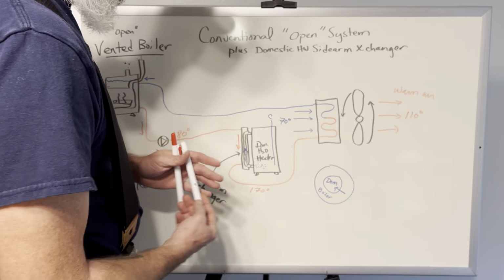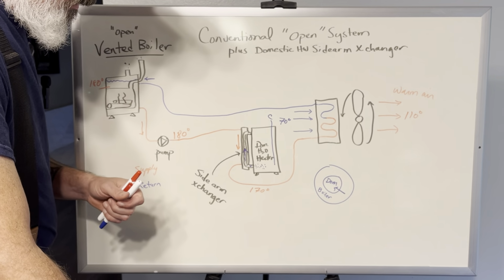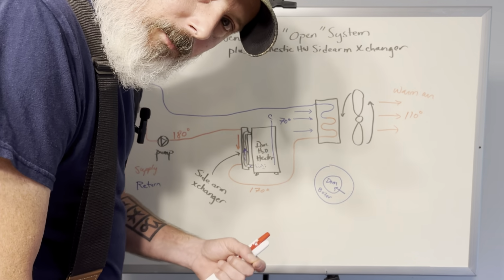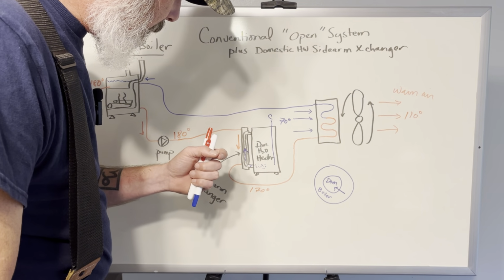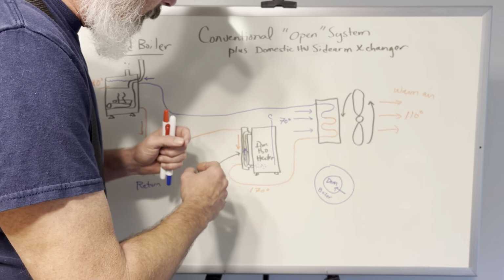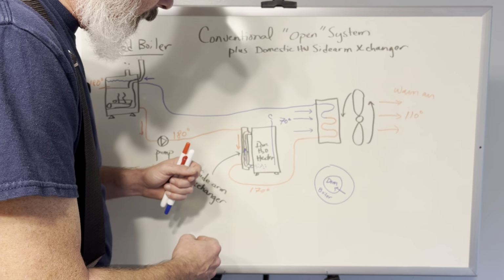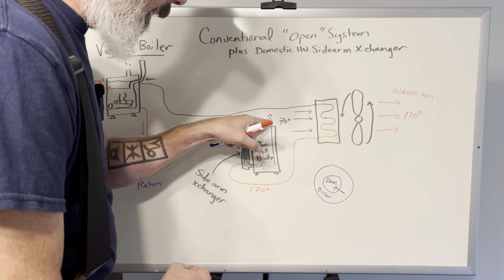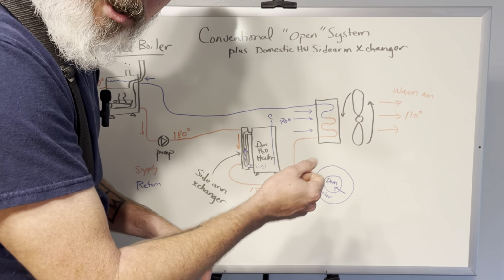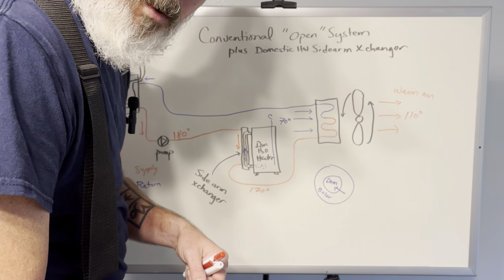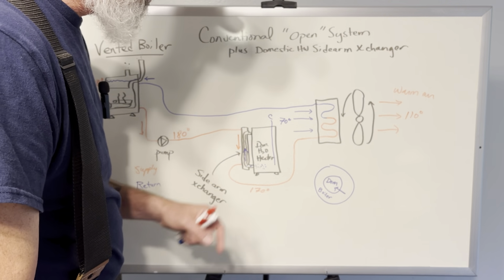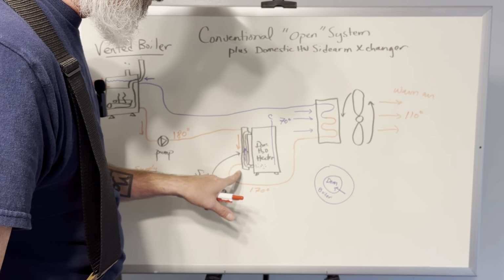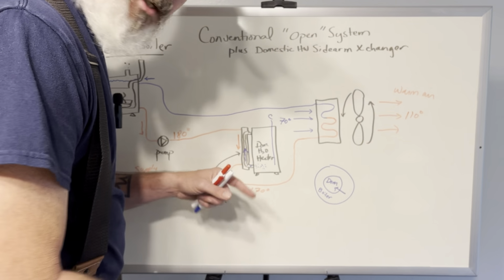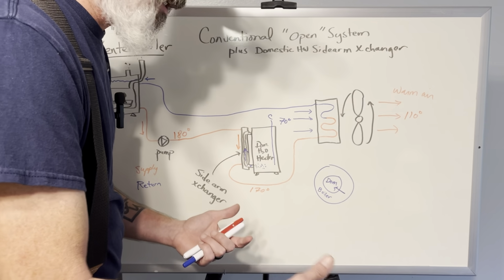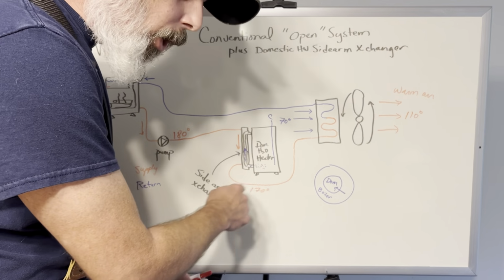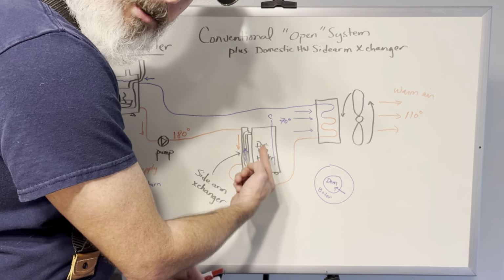So what happens here? A sidearm heat exchanger is a very slow recovery. It's not a fast process. It's not going to take 60-degree well water and instantly turn it into 110-degree water for your fixtures. It's not. So sidearm heat exchangers are used during an off cycle. So while nobody's taking showers, this is slowly going to recharge this domestic tank.